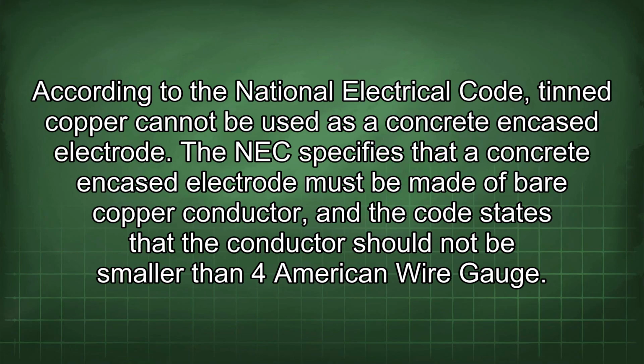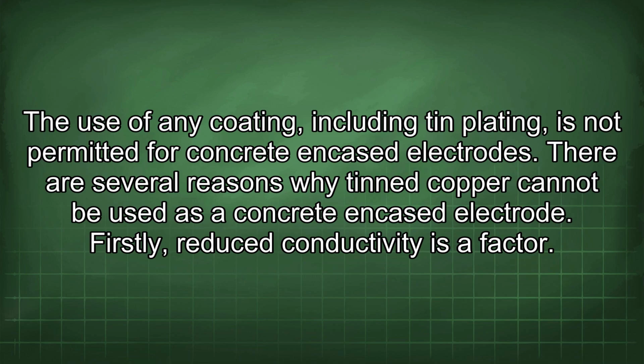According to the National Electrical Code, tinned copper cannot be used as a concrete encased electrode. The NEC specifies that a concrete encased electrode must be made of bare copper conductor, and the code states that the conductor should not be smaller than 4 American wire gauge. The use of any coating, including tin plating, is not permitted for concrete encased electrodes.